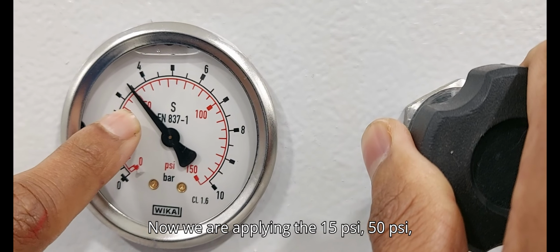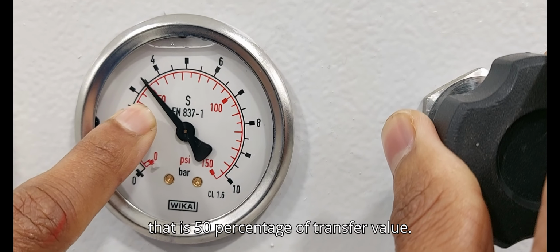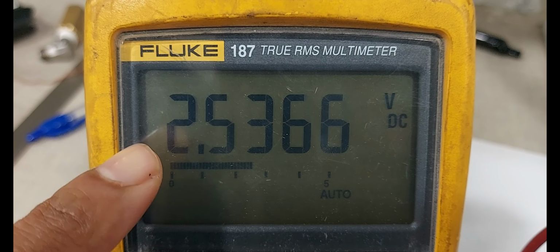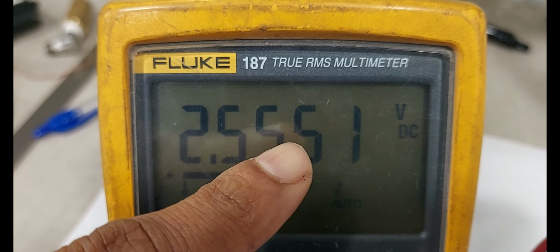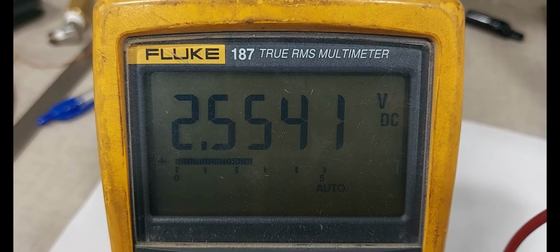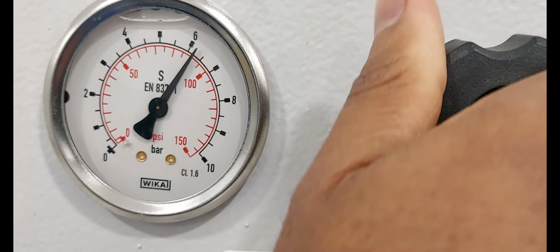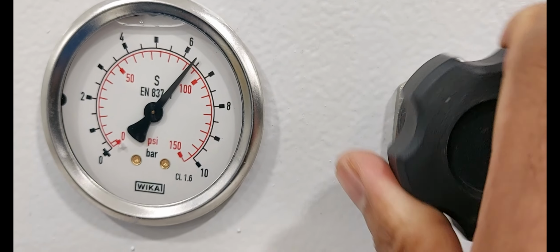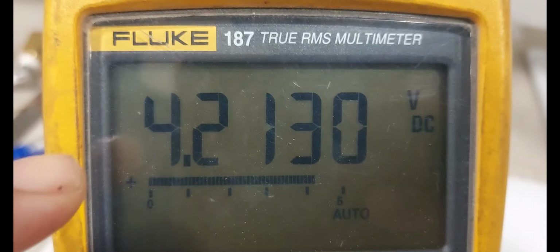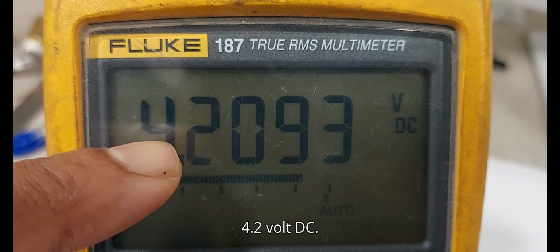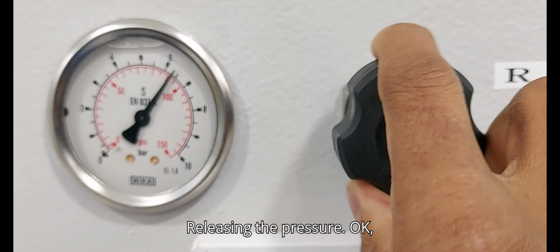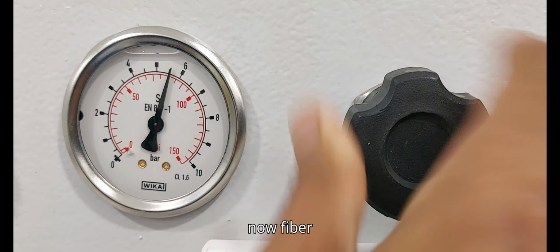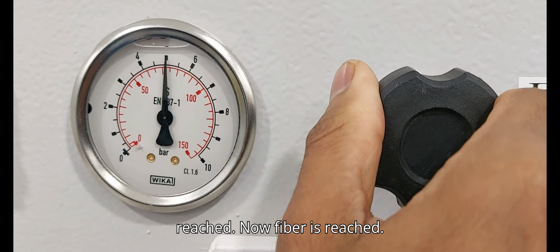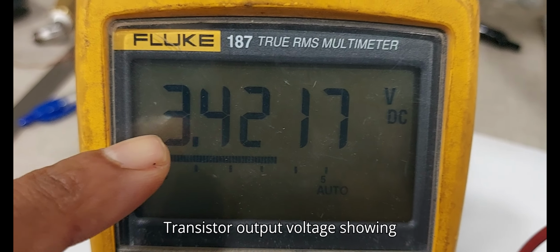Now we are applying 50 psi, that is 50% of transducer value. Now output is showing 2.5550 volt DC. To the full scale. Now transducer output is showing 4.2 volt DC. Releasing the pressure. Okay, now 5 bar reached. Transducer output voltage showing 3.42 volt DC.